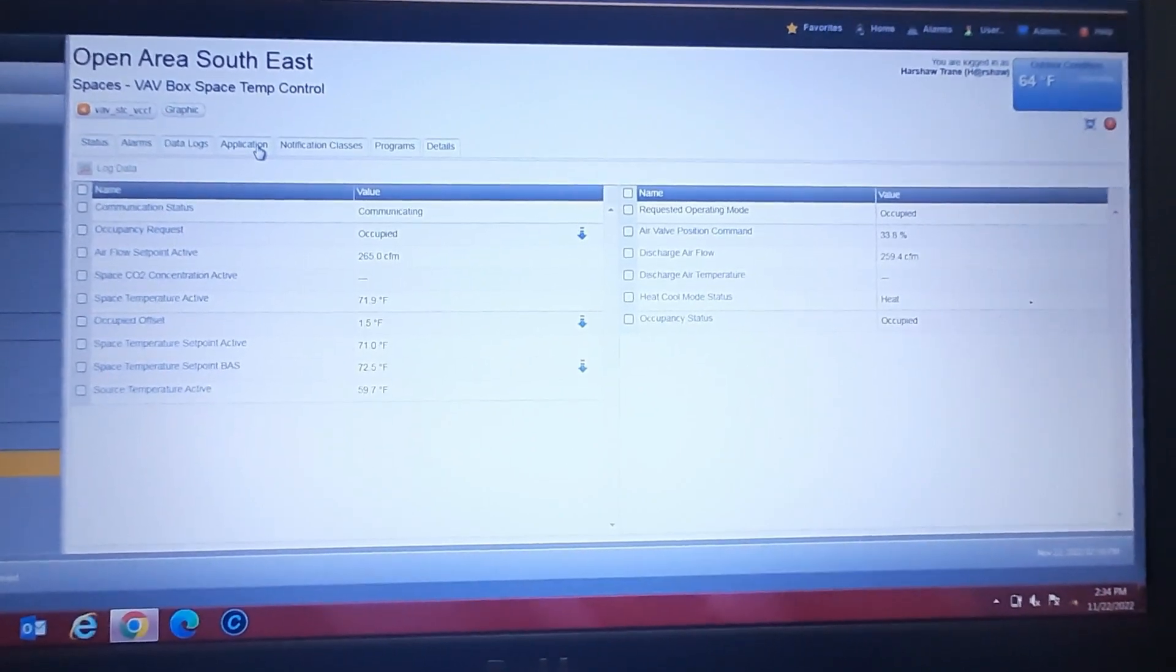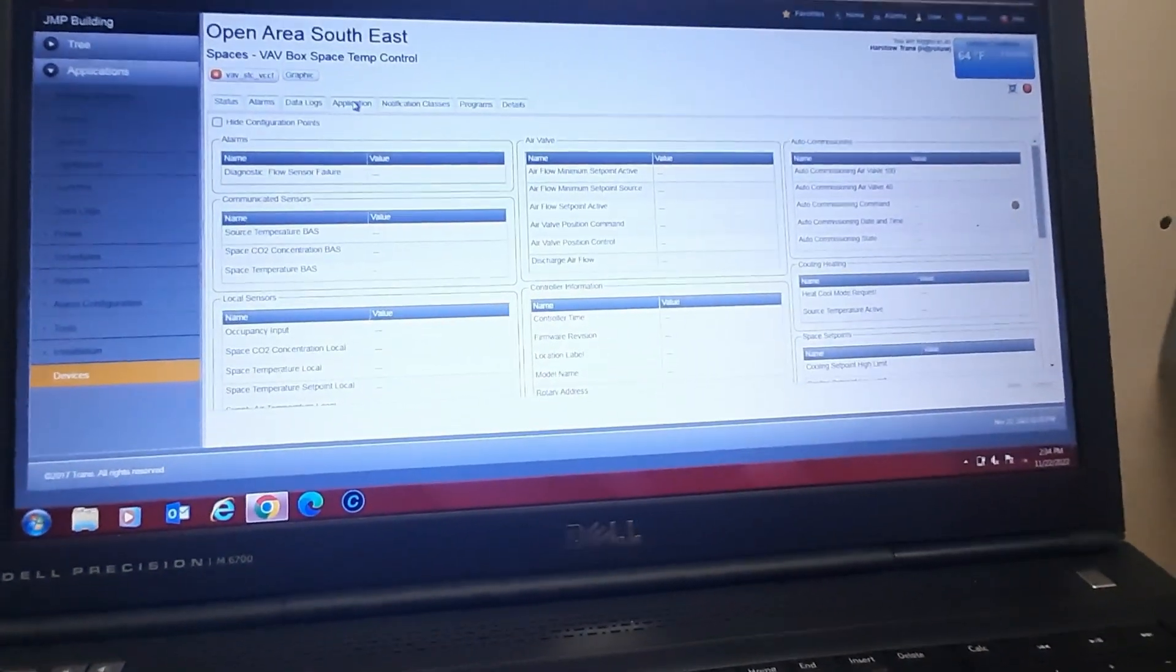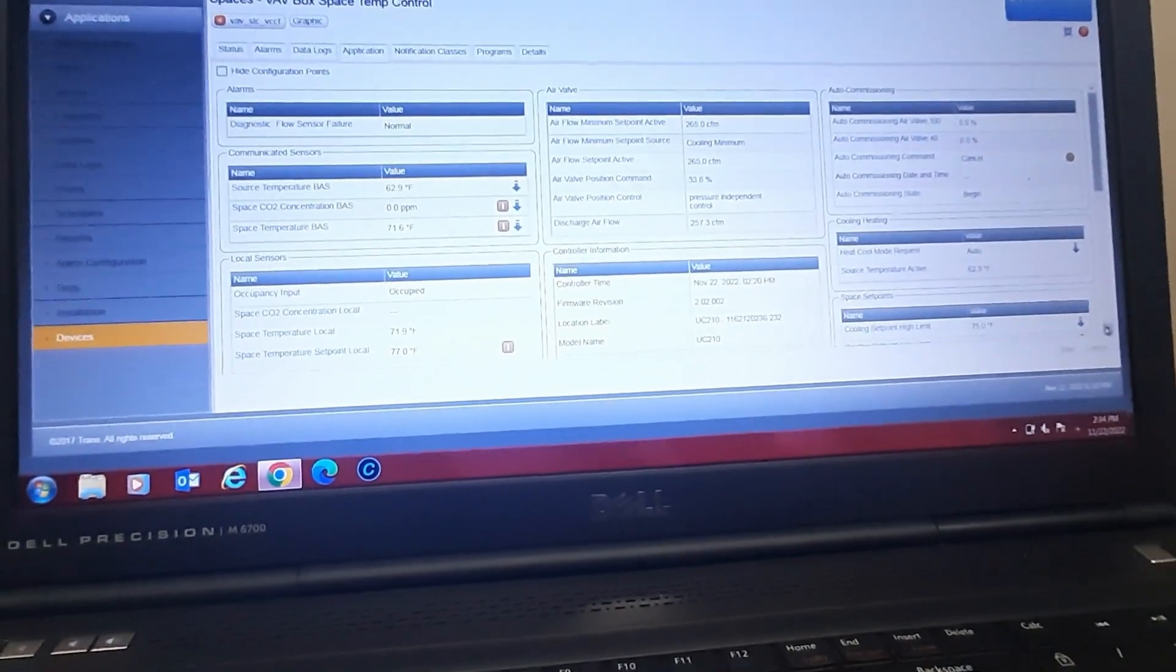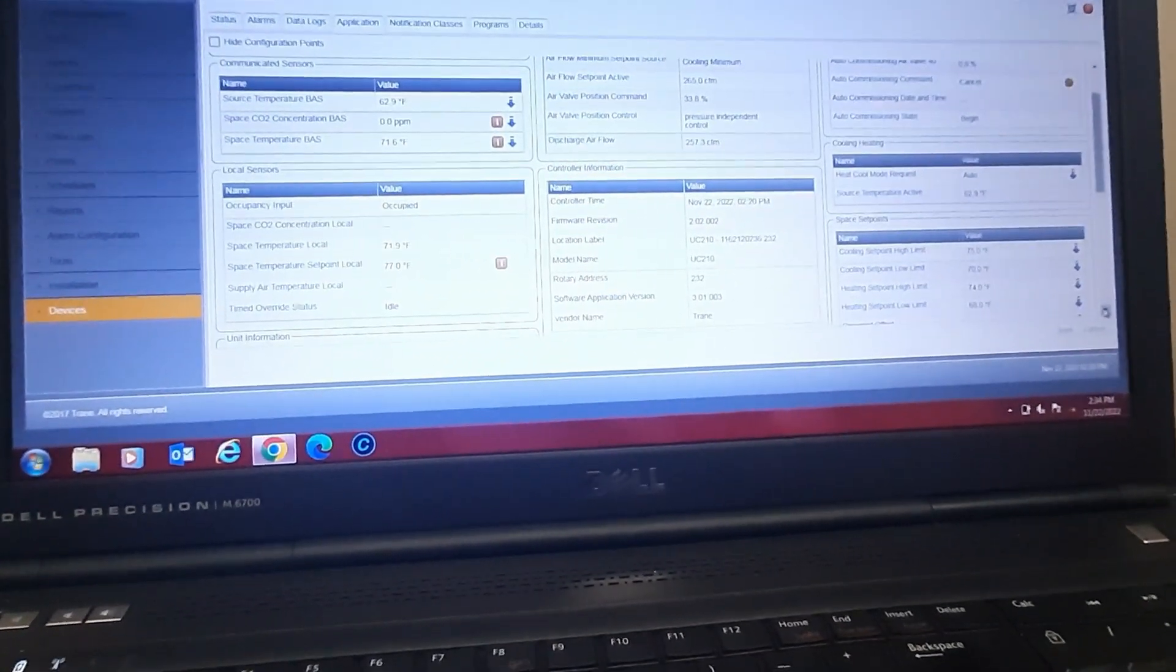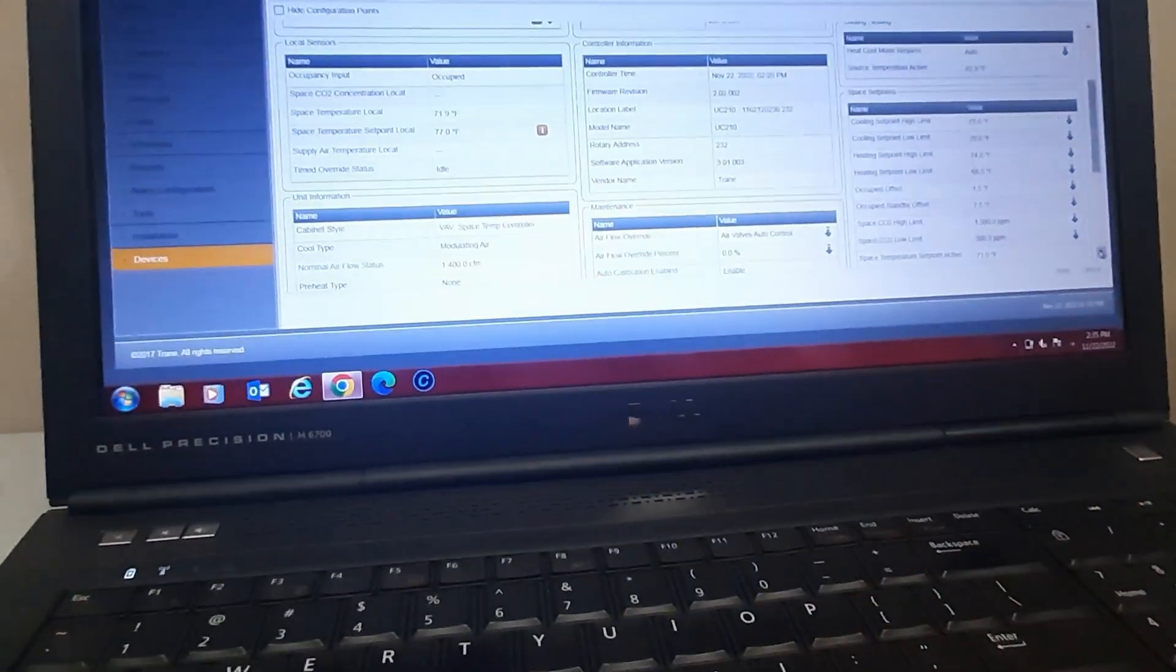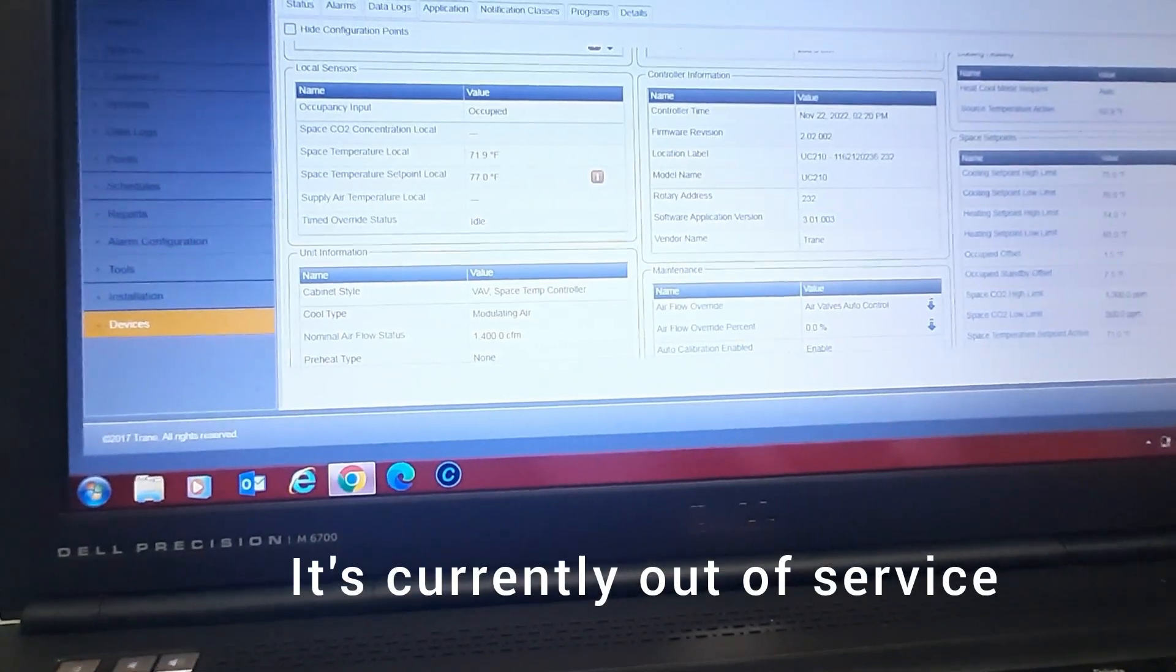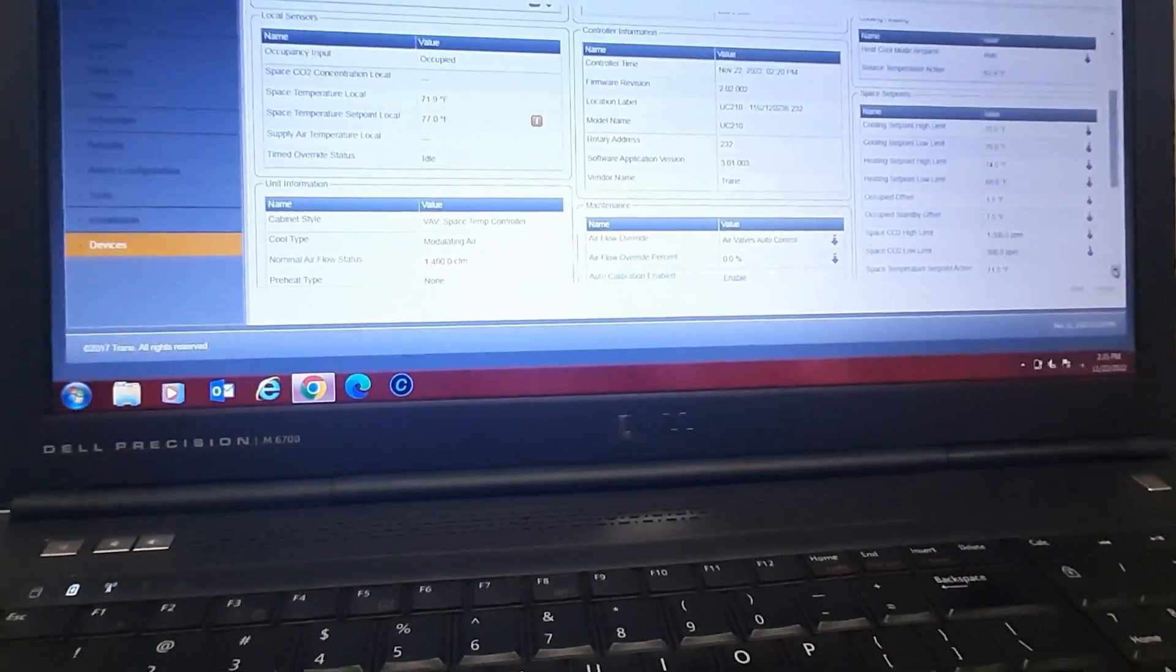So if we dig in and go to the application, we can look at our airflow set points and our temperature set points. I don't know why we would have set the max temperature to 71, but heating set point high limit 74, so we might increase that a couple degrees. See, because there's your set point local, it's showing 77. So we're going to increase that and get him closer to where he's actually set at.